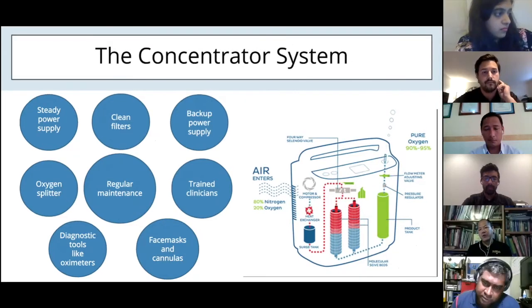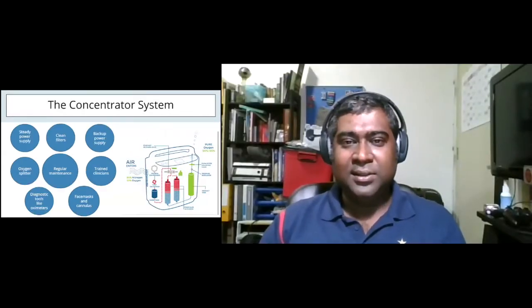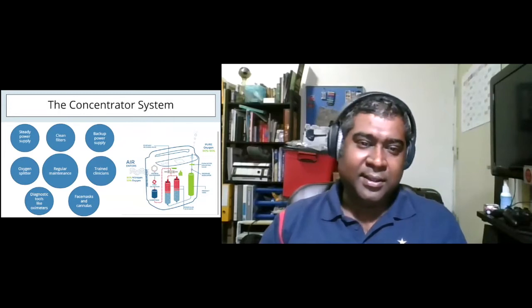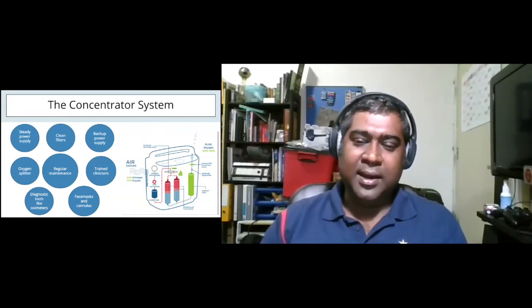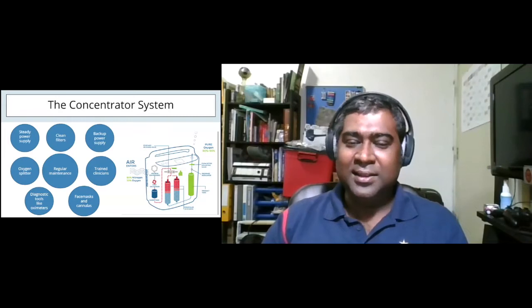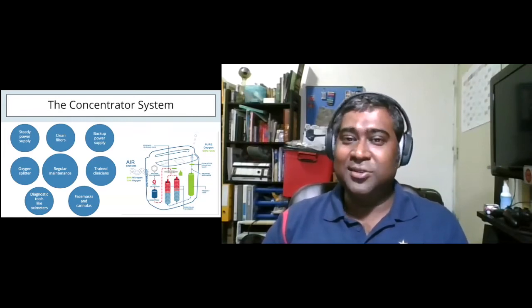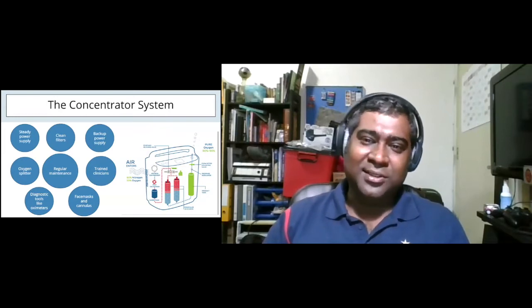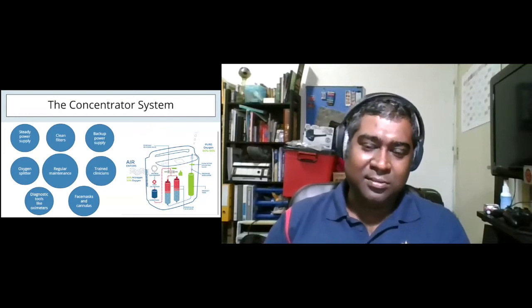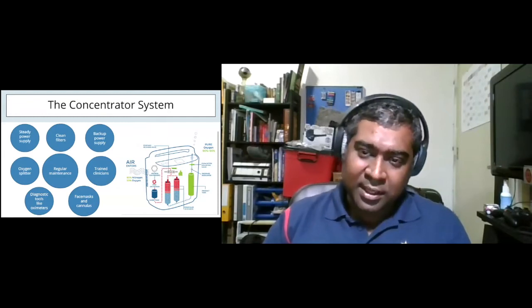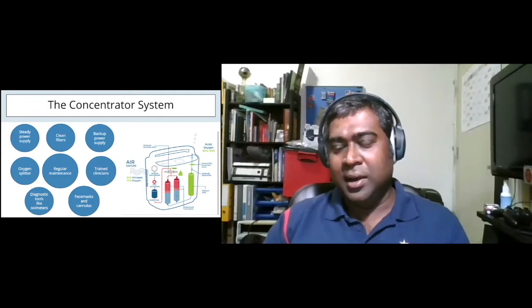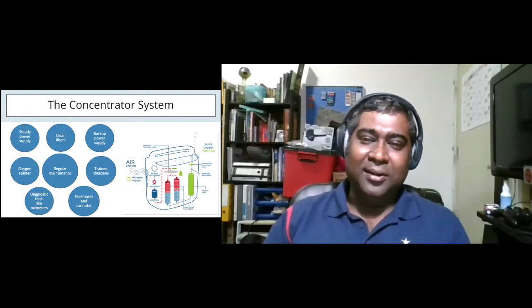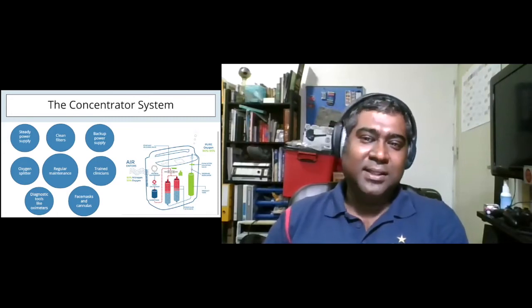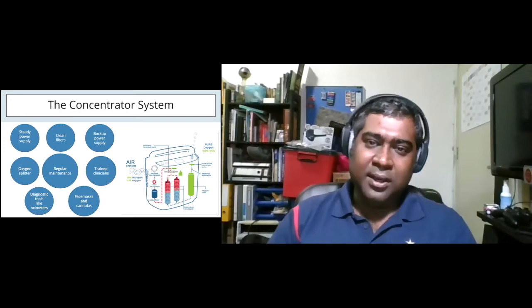Yeah, sure. Most of the concentrators that you see in the field, you're going to see a lack of maintenance, and they've never been tested. That's a normal thing that you're going to see. Ended up, the concentrator is not going to perform at all. So maybe you get 40% output, but they think the oxygen concentrator still works and they are using it, but you are not delivering the exact oxygen to the patient. So that's very common, and most oxygen concentrators have an alarm system that tells you exactly what the problem is, but they don't really look into that. So eventually the machine is not working properly.